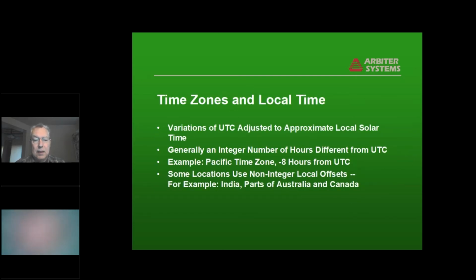Local time is another issue that is a problem between different utilities in different regions. Some utilities are large enough to actually span different time zones within their own service area. Others don't, but they coordinate with other utilities that are in different time zones when doing fault analysis. And it's based on UTC, with almost all places, but not all, an integer number of hours different. In the Pacific time zone where Arbiter's factory is located, it is -8 hours from UTC, which means it's 8 hours later in London than it is in California. And that's in the winter. In the summer, it's 7 hours difference. So it's not always the same.